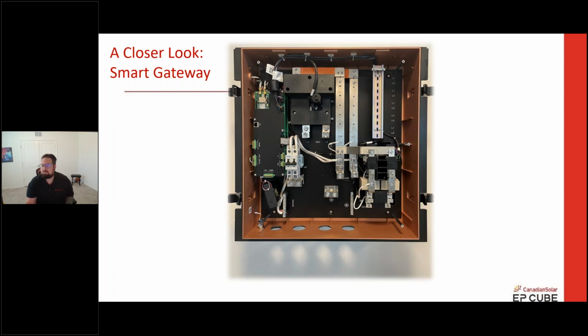If you want to set this up as a whole home system, you can take that from the meter, or rather a 200 amp main panel, and cut in between that to power the whole house that way. But if a backup loads panel is more convenient, you can do that too. Those terminals in the bottom right corner are what Justin was referencing.